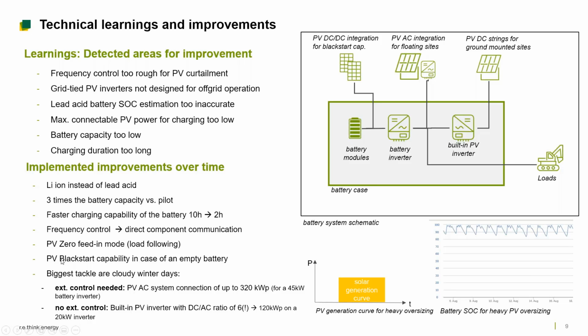And as I explained before, the DC-DC connection is quite important, because what do you do if you wake up in the morning and your battery is empty and you want to start it up? There's solar energy, but still your battery cannot start up because the 50 Hertz is missing to have these PV inverters running. In this case, you would always need an external grid, an external genset, or some AC source to really start your battery. That's why we included the DC-DC connection to have a black start capability in case of an empty battery.